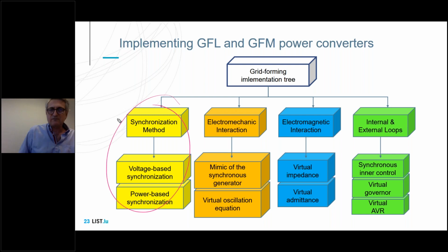One of them would be defining how we synchronize. We can synchronize based on power balance, but we could also synchronize based on voltage. We can have several PLLs - some fast PLLs to react to faults, some slow PLLs for reacting to electromechanical dynamics. That is perfectly feasible. In the same manner, it would be possible to determine the electromechanic behavior of the grid forming converter.